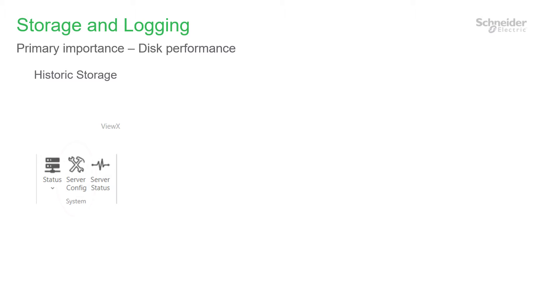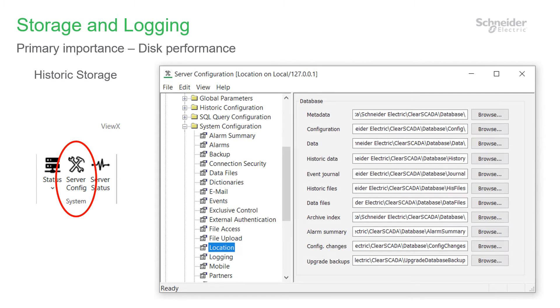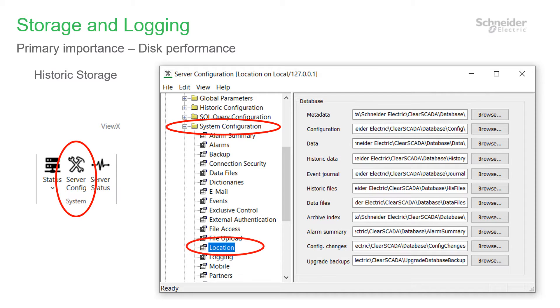You can set up the location of the various GeoSCADA database sections using the server configuration tool. Select System Configuration and then select Locations. By default the locations are in Program Data on the C drive. To change these settings you'll be asked to restart GeoSCADA. You must also move the files themselves if you wish to keep them in the database. I've highlighted the historian folders here with stars.